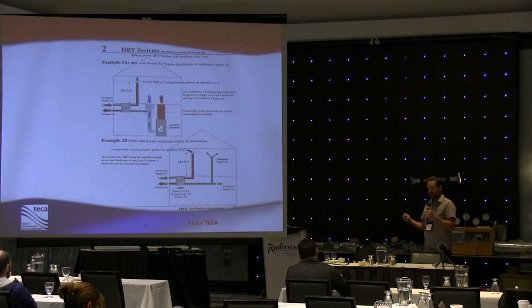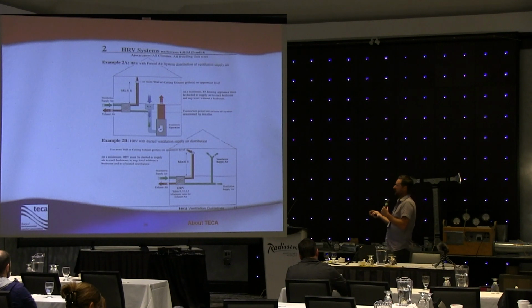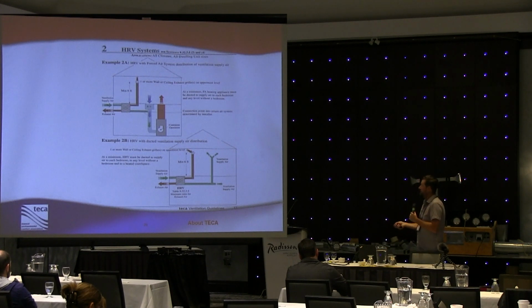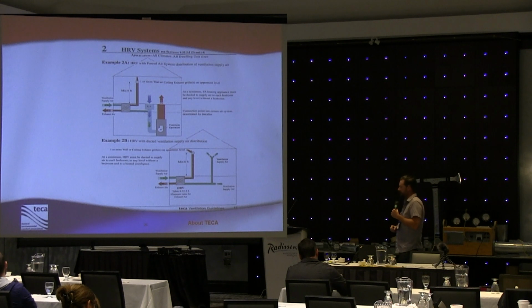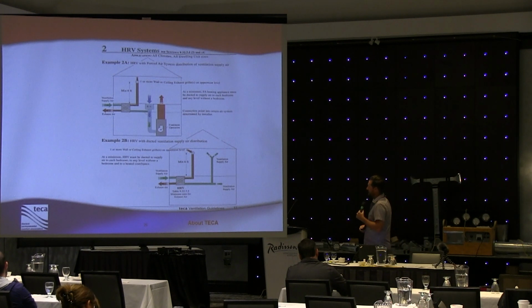Latent moisture, when it's in this airflow, contains a lot of energy. So when we allow some of that moisture to actually pass through into our fresh air that's coming in, we're going to collect a little bit more. We're going to pick up a few percent of efficiency on that type of unit.